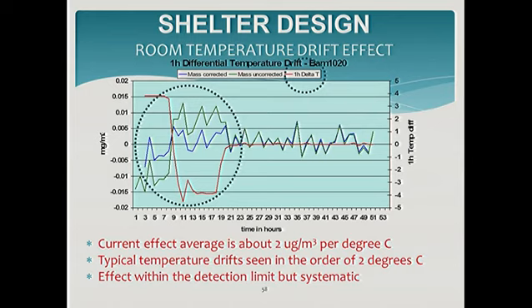The conditions for more accurate resultant concentrations are greatly improved when using the smart heater and when room temperature control is tightly controlled. Keep in mind that changes in room temperature will vary the relative humidity on the BAM tape, and this may affect the resultant mass concentration calculations.